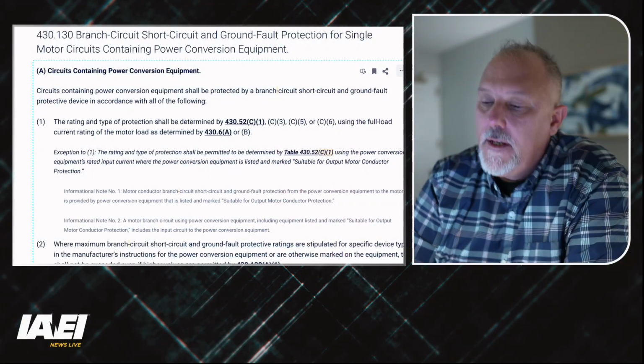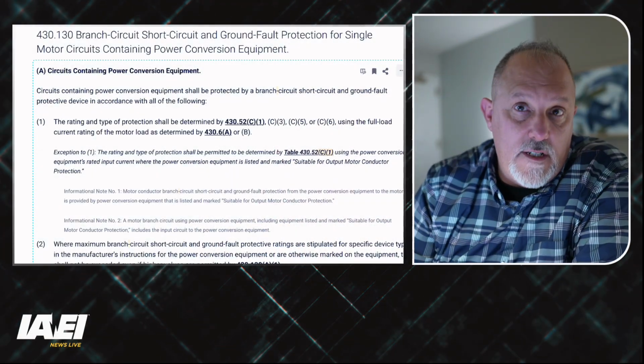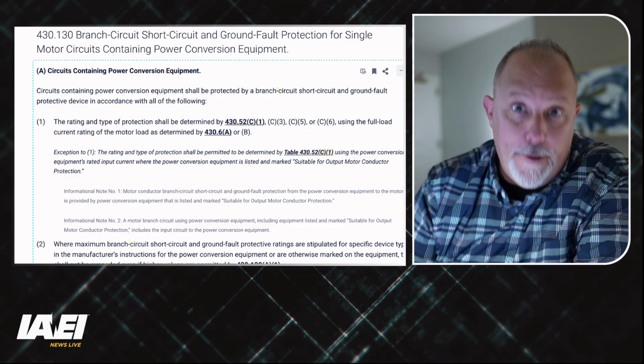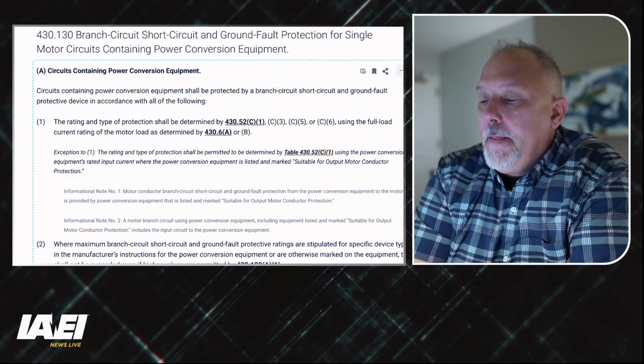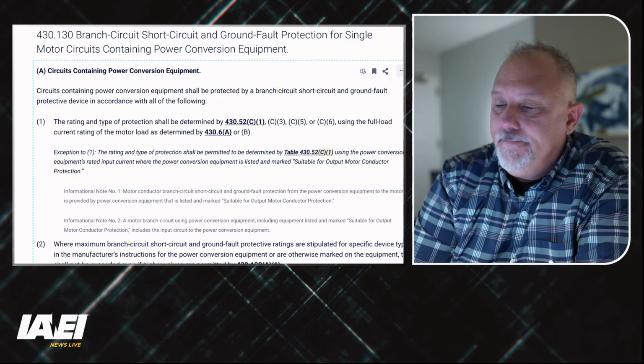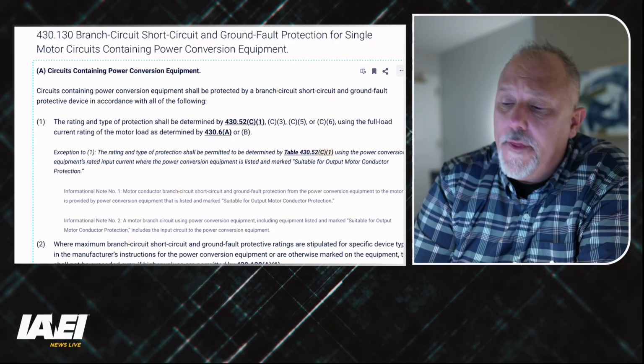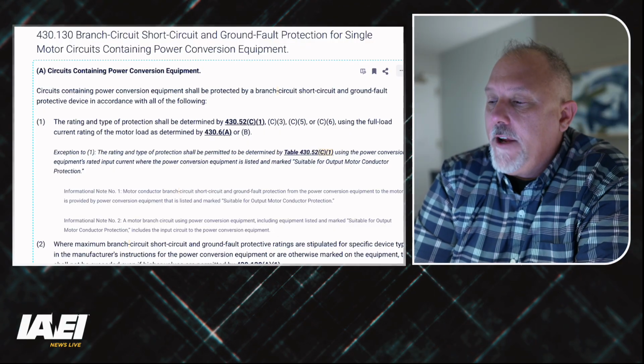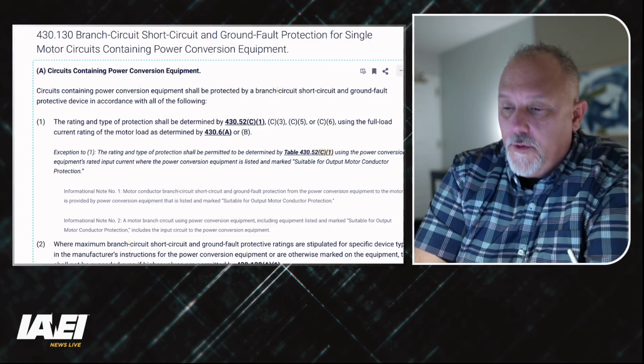You have a disconnecting means, and here we go. Branch circuit, short circuit, and ground fault protection for single motor circuits containing power conversion equipment. This is 430 dot... Dadgummit, I'm doing the wrong one. It is really late, and I'm really tired, so forgive me. So 430.130, branch circuit, short circuit, and ground fault protection for single motor circuits.